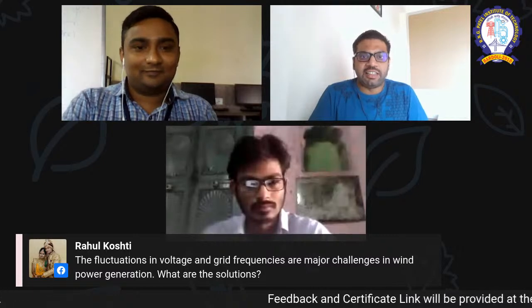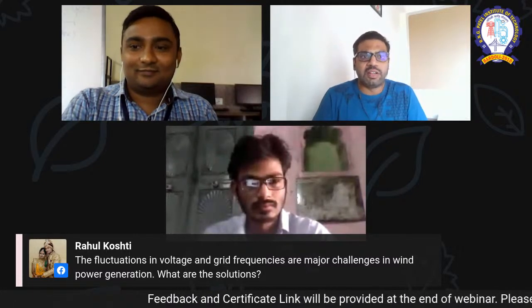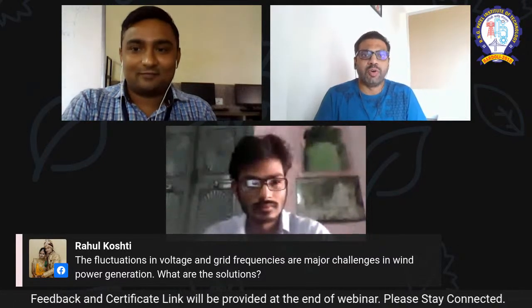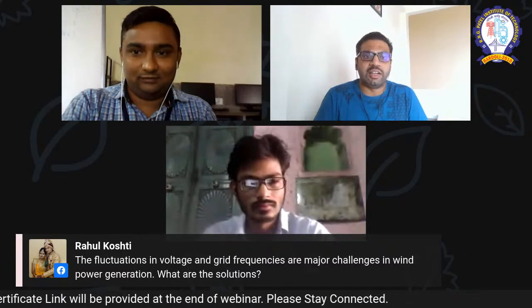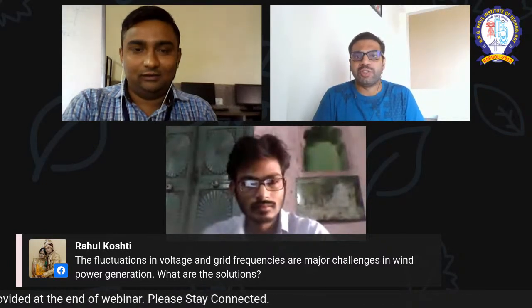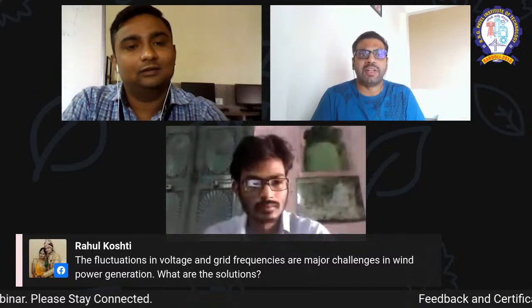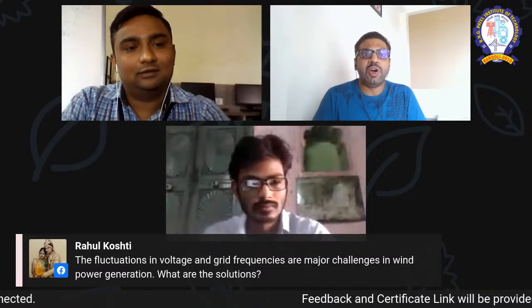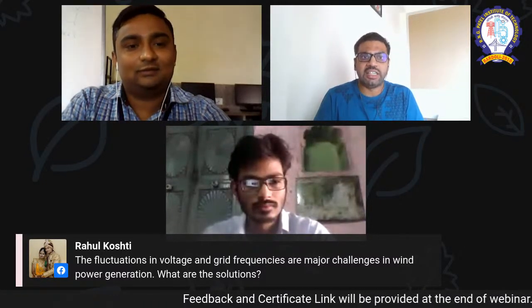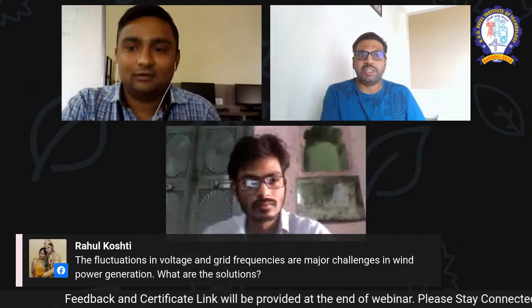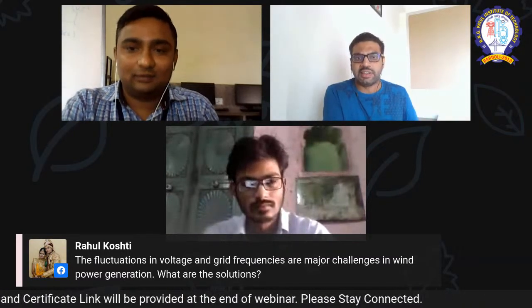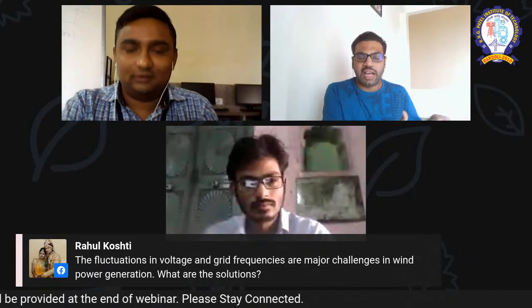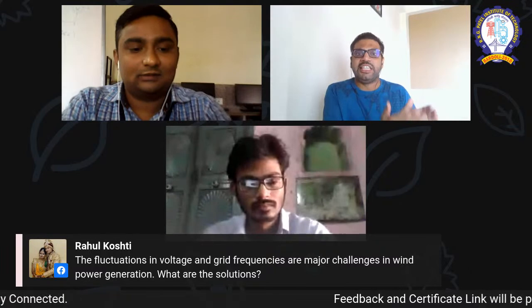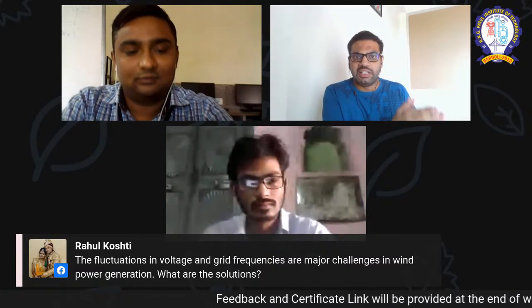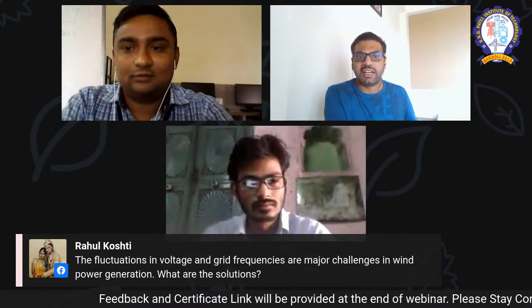Actually, it requires deep knowledge, but I will try to cover it in three to four lines. First of all, there are two kinds of fluctuations. In case of voltage fluctuations, the inverter will take care of them. Like a solar inverter, there is a big window available, that is 10% of 680 volts in the system, which I just discussed. That is 68 plus and 68 minus. That voltage is taken care of by the inverter assembly.